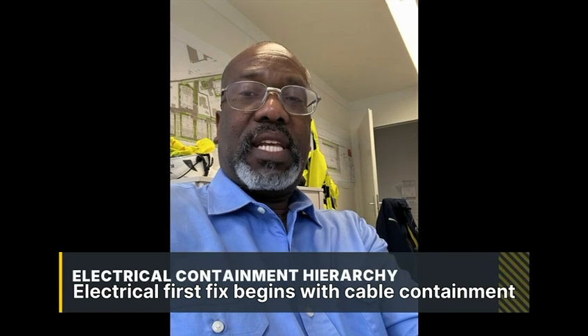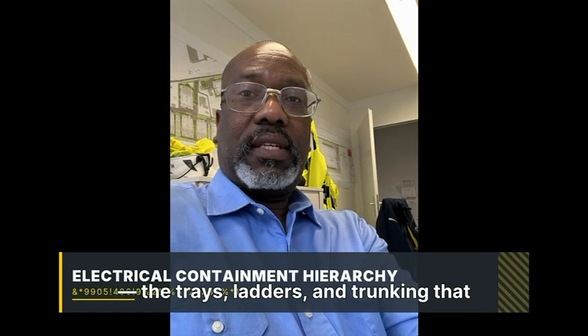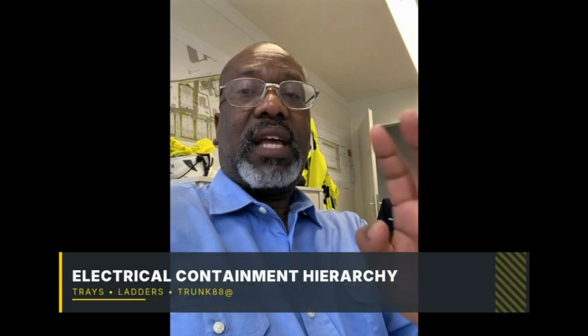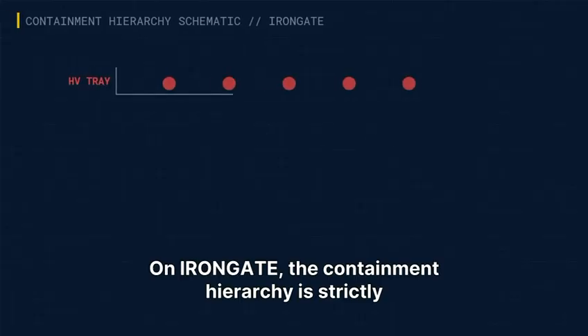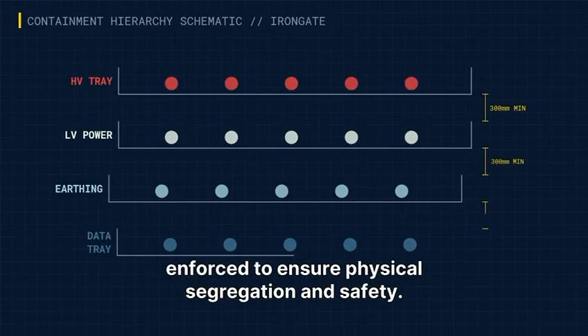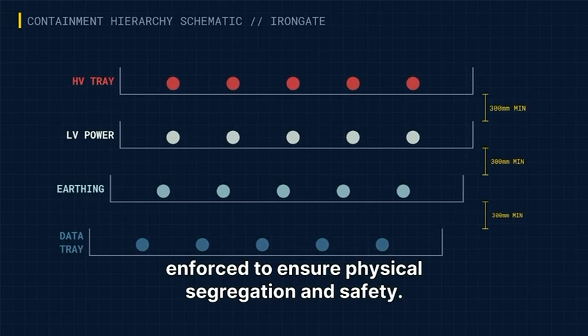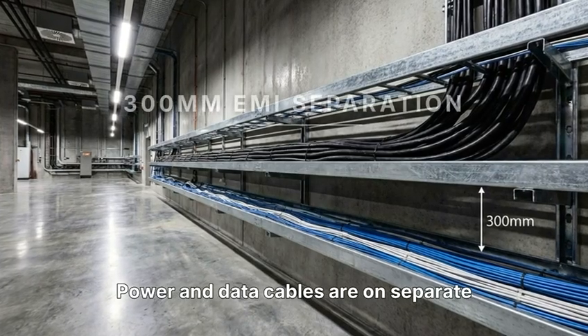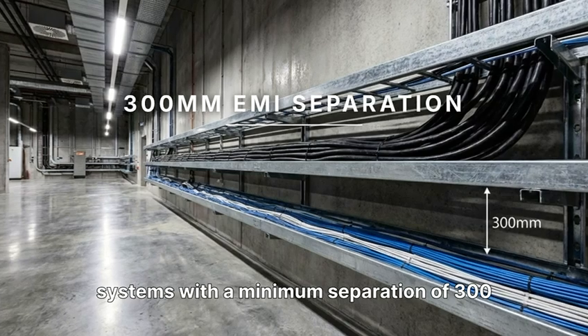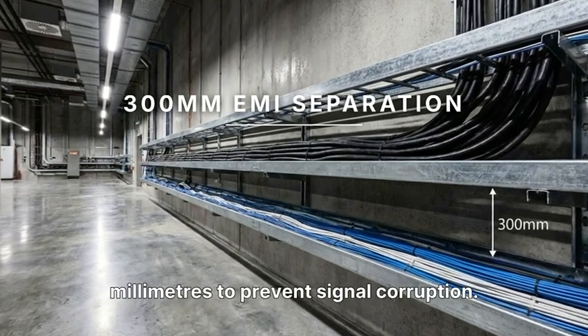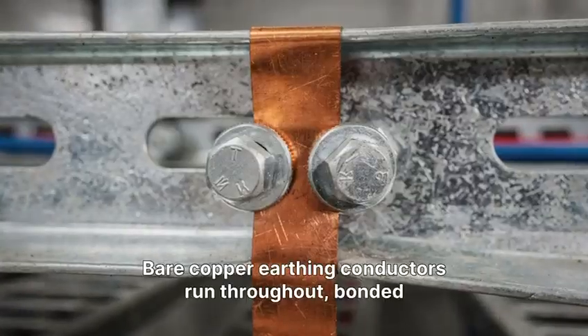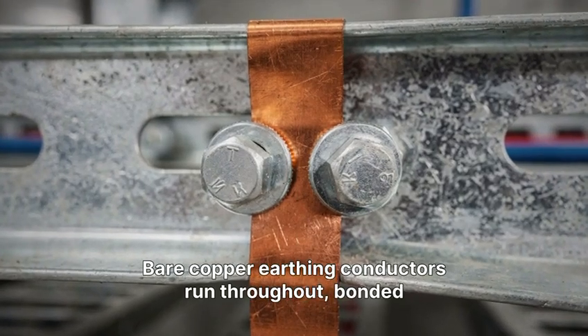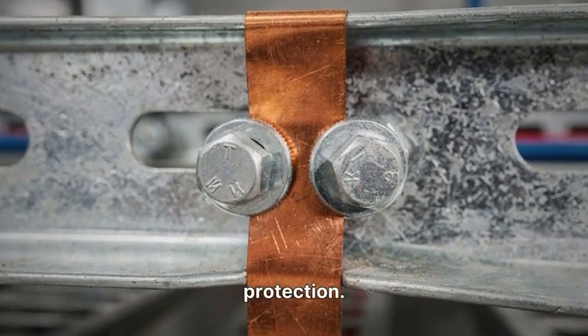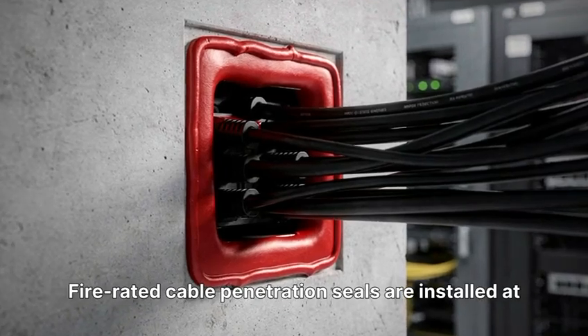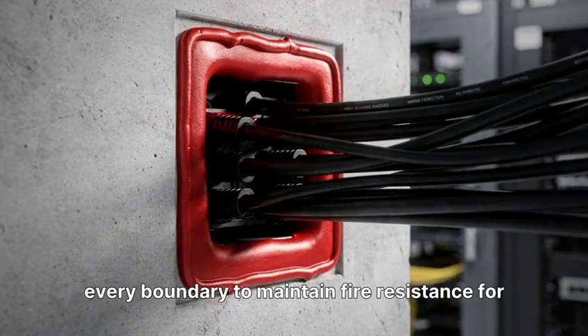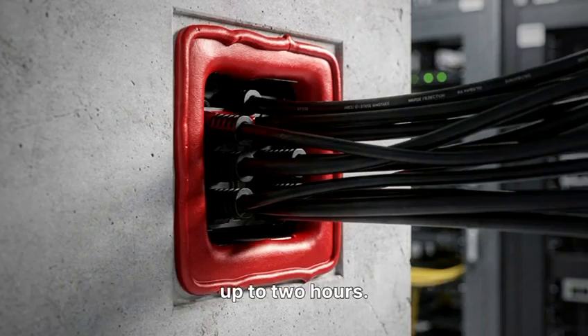Electrical first fix begins with cable containment, the trays, ladders, and trunking that carry the power. On IRONGATE, the containment hierarchy is strictly enforced to ensure physical segregation and safety. Power and data cables are on separate systems with a minimum separation of 300 mm to prevent signal corruption. Bare copper earthing conductors run throughout, bonded to each tray section for full equipment protection. Fire-rated cable penetration seals are installed at every boundary to maintain fire resistance for up to 2 hours.